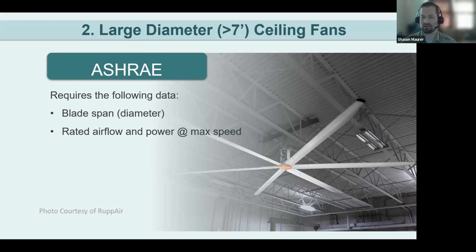Frequently, these are only operated at full speed during the summer and at reduced speed during winter to provide destratification in atrium spaces, while minimizing the wind chill factor that might happen in the wintertime. At this time, there's no required efficiency requirement for these systems. So the standard is trying to bring that to attention and put some kind of standard in place. And so having a published span, airflow, and power may enable future efficiency requirements to be established, or just may encourage design teams to select more efficient equipment as they're looking at options for these types of fan systems.